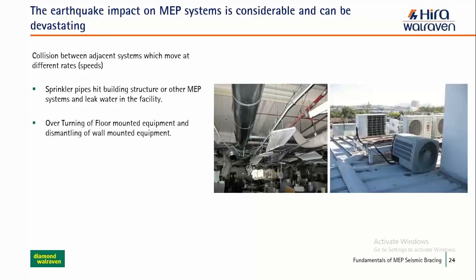This is specifically for the floor mounted system. Floor mounted equipment has its own effects due to earthquake movement. Every piece of equipment has its center of gravity, and because of that, the equipment could fall down due to movement at the base, creating a risk of overturning for floor mounted equipment.